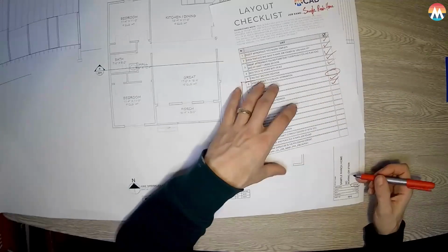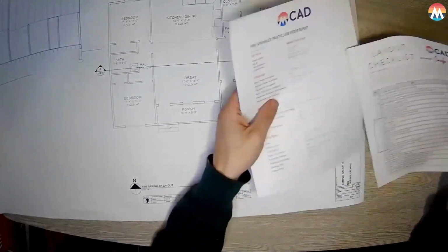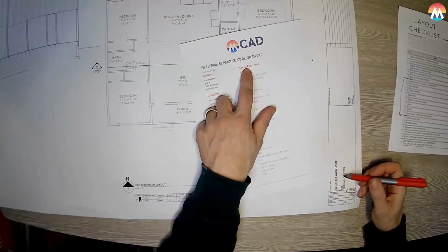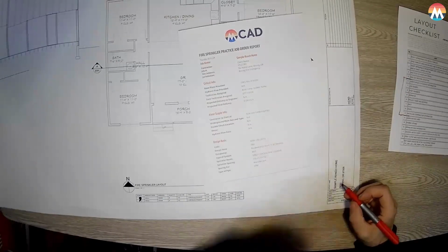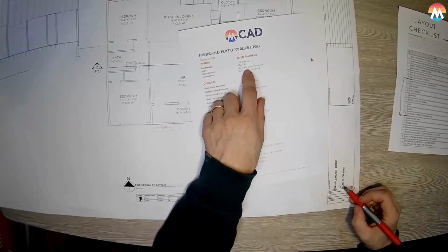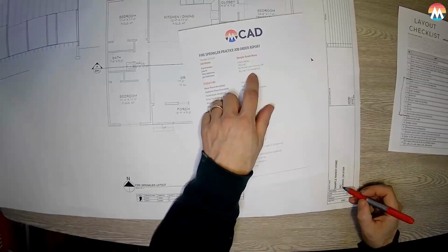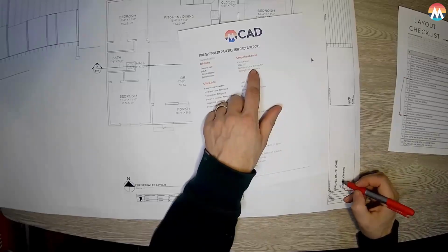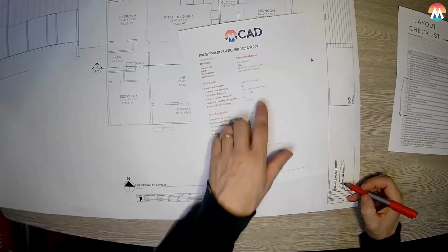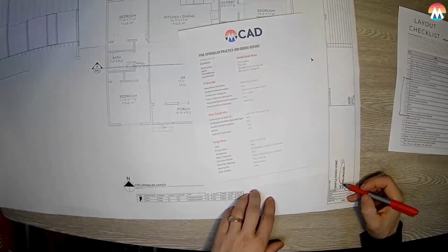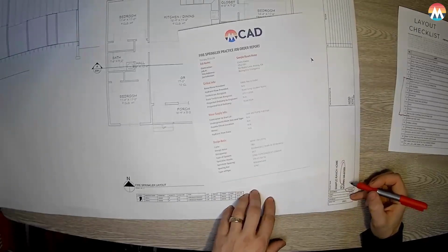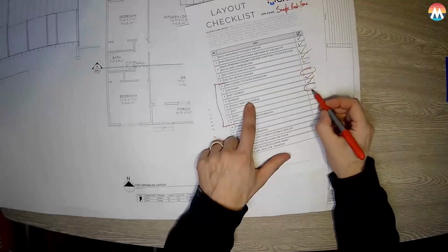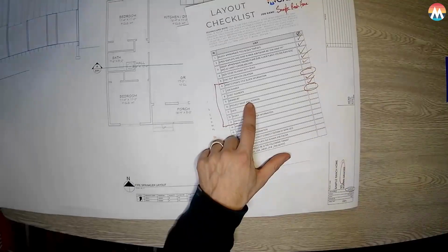Project name and address. So we've got this sample ranch home. That looks good. That matches our job order report. Now the address, though, it looks like it's supposed to be No Name Lane in Boring, Oregon, and they have that, but they just have not No Name Lane. So let's circle that. That's incorrect. And let's see. What else do we have on here? That was project name and address, so I'm not going to cross that off yet until that gets corrected.